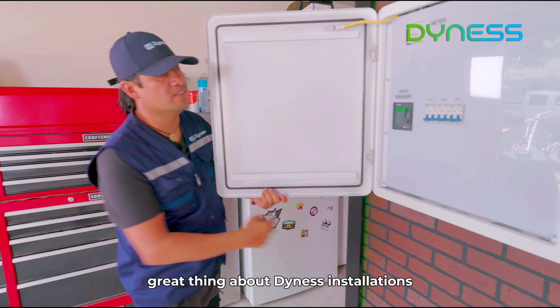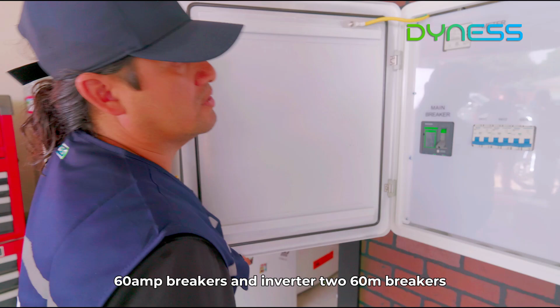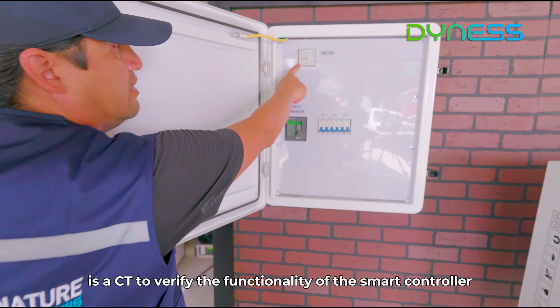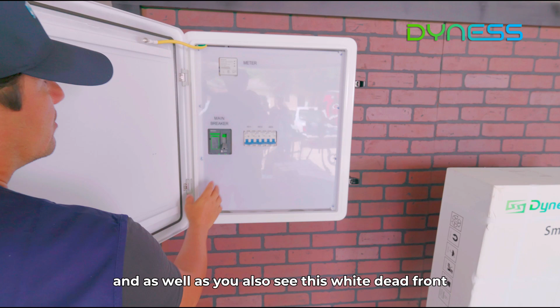Great thing about Dyness' installations, every one of their smart controllers is equipped with a 200 amp main breaker. It's also installed with 2 individual breakers: inverter 1 60 amp and inverter 2 60 amp. As well, you'll also see that it has an electricity meter, which is a CT, to verify the functionality of the smart controller. And you also see this white dead front. And as well you also see the grounding between the door and the structure of the actual smart controller.